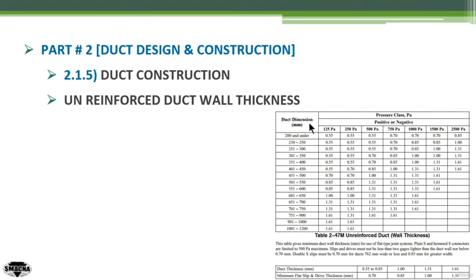The duct dimension represents the row and the pressure classification represents the column. Intersecting the row for 70 cm with the 500 Pascal column gives the sheet metal thickness. For this example, the sheet metal thickness is 1.31 mm.